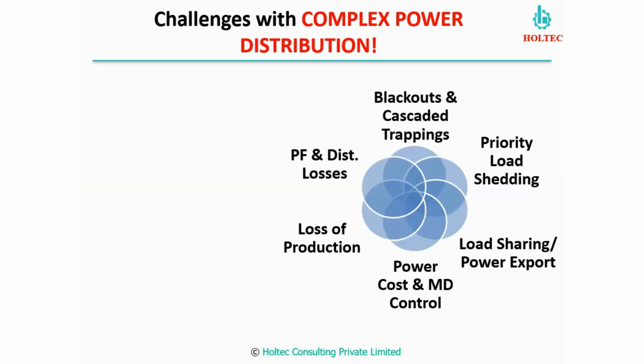Then the other challenge is load sharing. Here we can have two types of condition. One condition is when we are running in parallel with the grid. Normally, what is the scenario nowadays? We draw minimum power from the grid and try to get our own generation to the maximum. But what is happening? You have a fluctuating load. Your plant operation is not fixed. Sometimes 20 megawatt is running, sometimes 50 megawatt is running. Like this, there is a change.